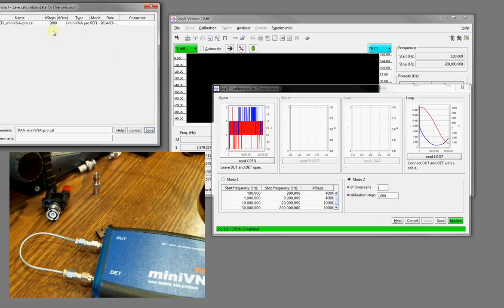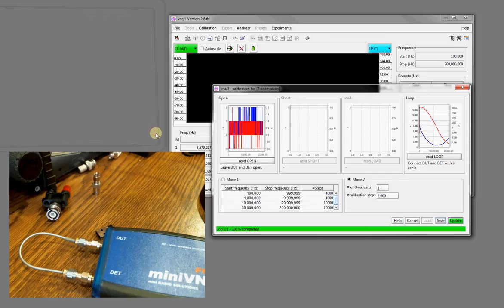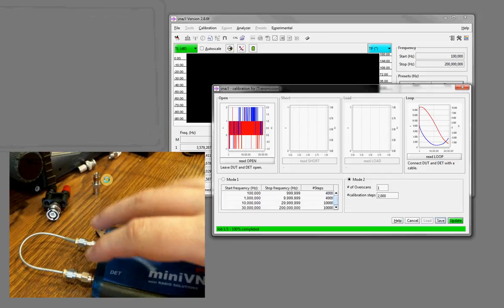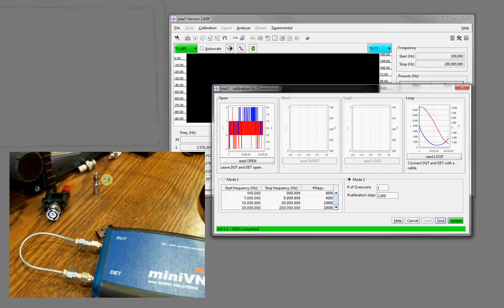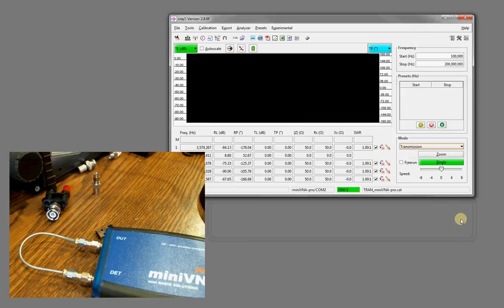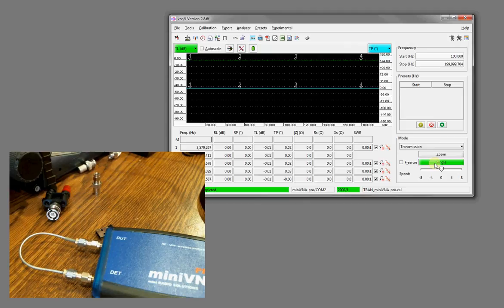You already see the calibration from earlier, and you can save all different types of calibrations. For example, if you're using SMA cables terminated with SMA connectors, and you want to calibrate from the end of the cables, or if you have a bunch of adapters or attenuators hooked up to it, it allows you to. I'm not sure if you can calibrate with the attenuators in line, but it just allows you to have all different sorts of calibration files. I tend to calibrate the unit whenever I hook it up to the computer and use it. So we're going to update, and now we're ready to measure the transmission loss and phase.